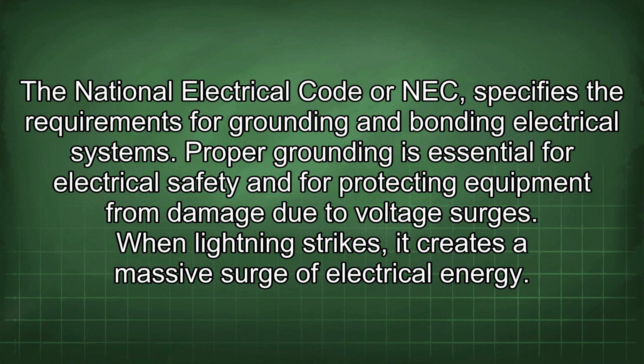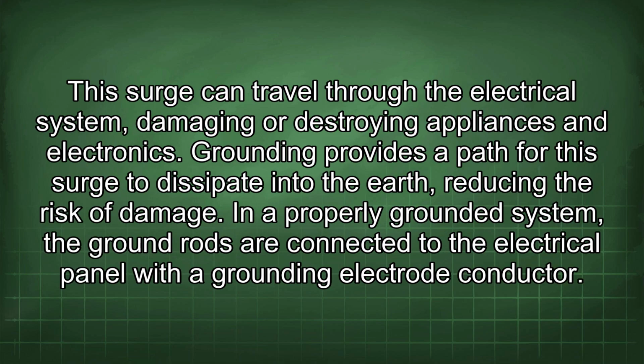The National Electrical Code, or NEC, specifies the requirements for grounding and bonding electrical systems. Proper grounding is essential for electrical safety and for protecting equipment from damage due to voltage surges. When lightning strikes, it creates a massive surge of electrical energy. This surge can travel through the electrical system, damaging or destroying appliances and electronics. Grounding provides a path for this surge to dissipate into the earth, reducing the risk of damage.